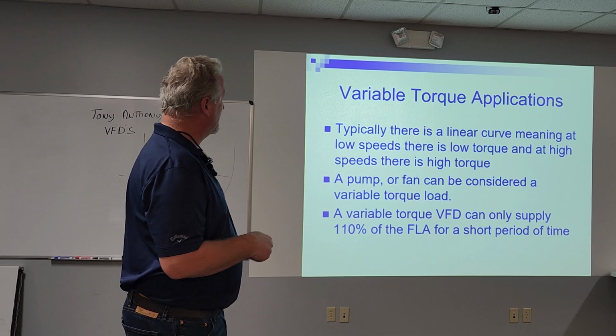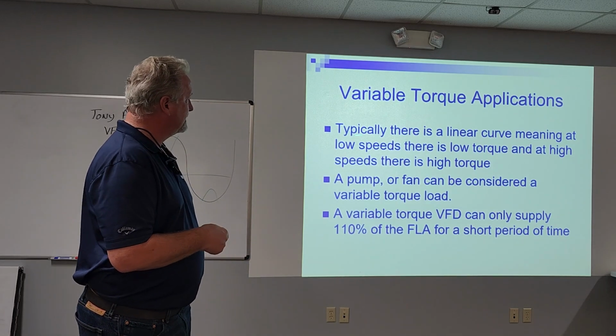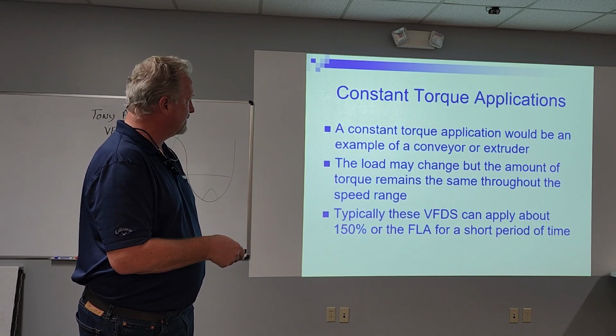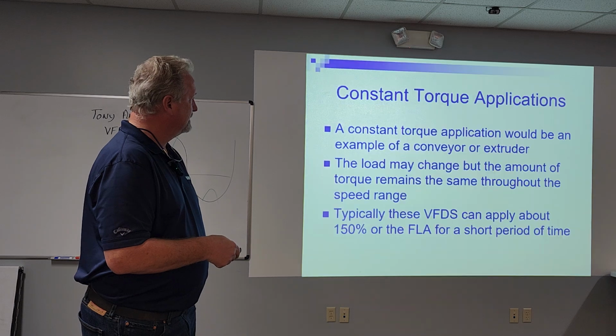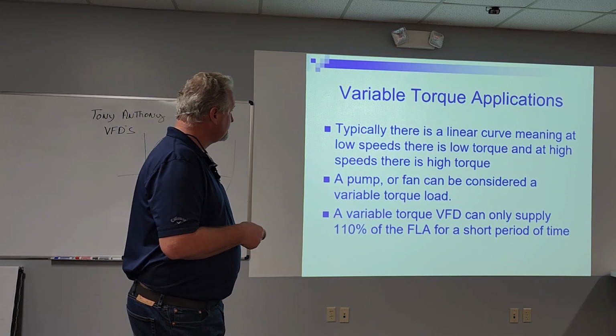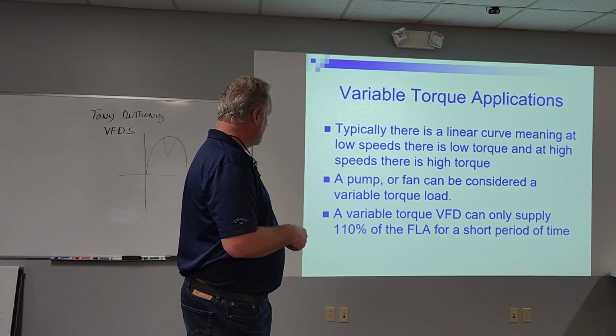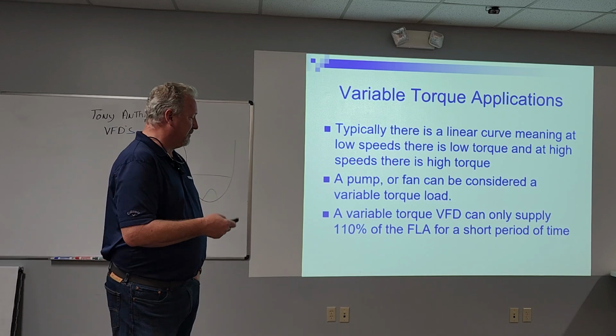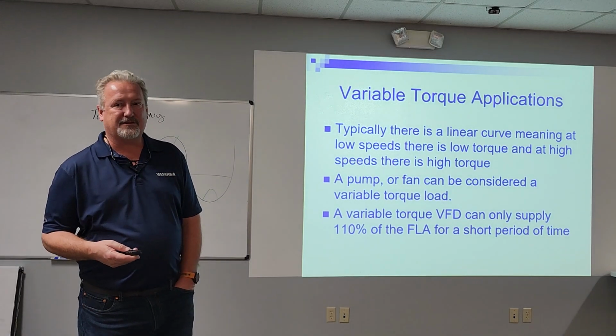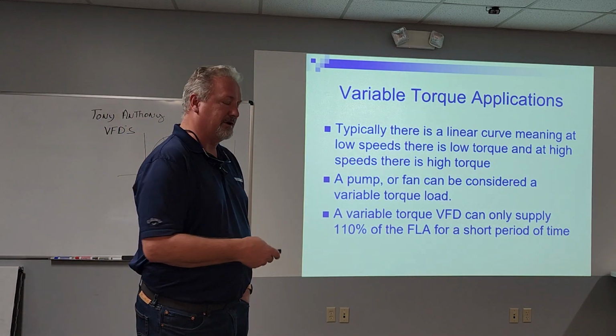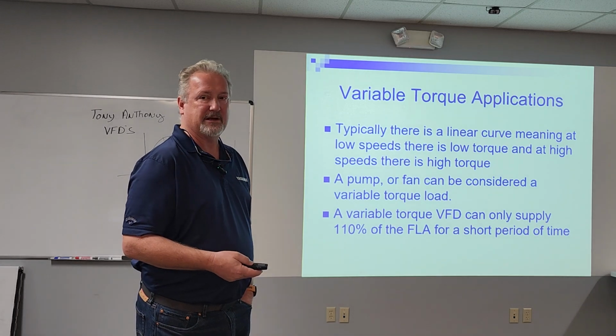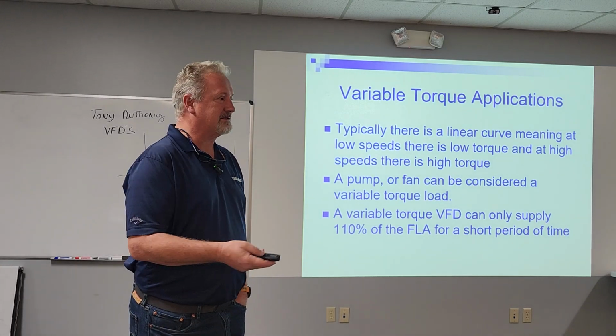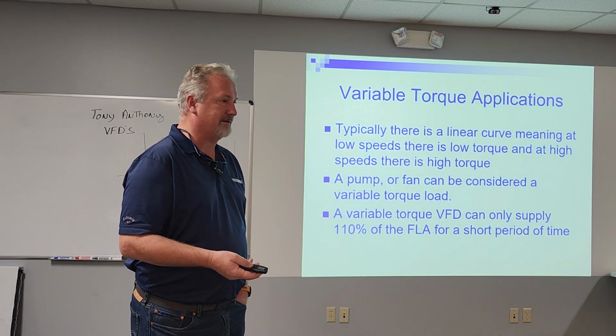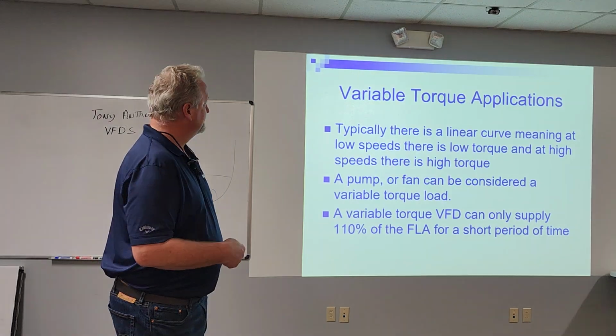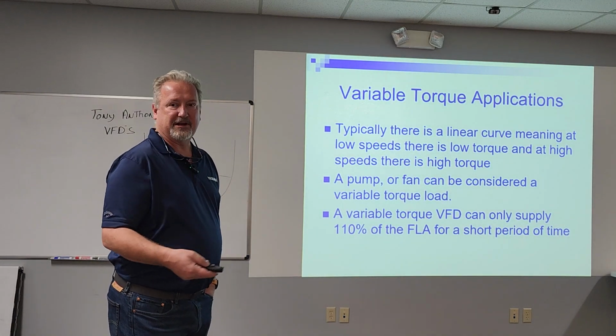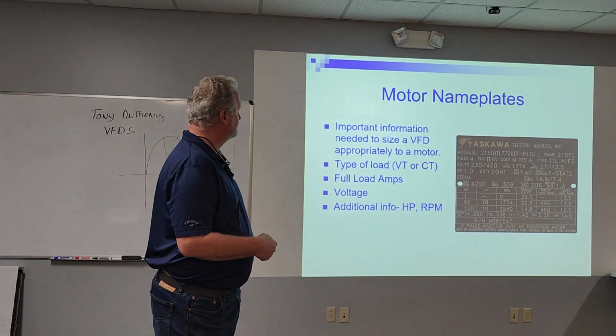So we kind of go through this. We've already kind of covered this. Variable torque applications, linear curve. That's that curve we talked about here. A pump or fan can be considered a variable torque load. In the VFD, we only set it for 110% overload. So that drive is sized that way because we don't expect to have any torque at the bottom of it running at slow speeds. And in most of your applications, I doubt you ever go below 20 or 25 hertz, because below that you're not doing any work anyway. You might as well just shut off.